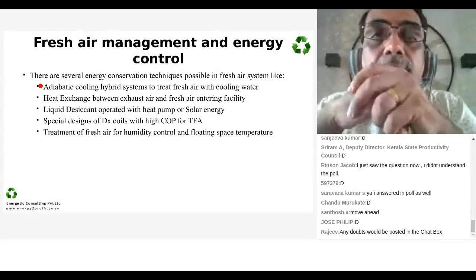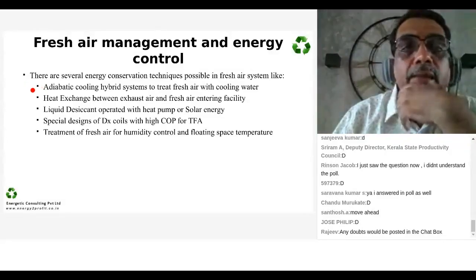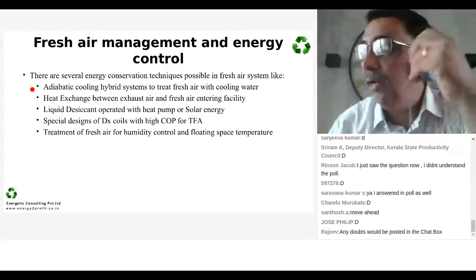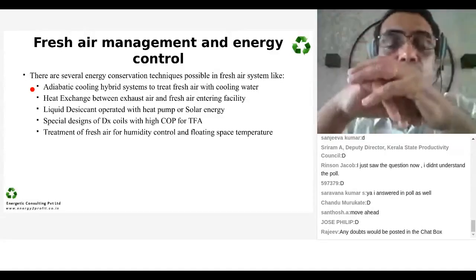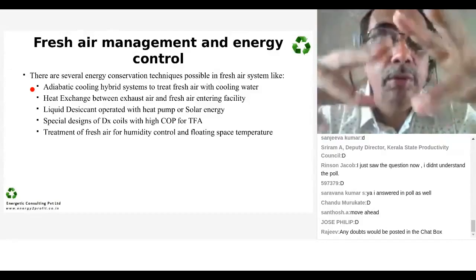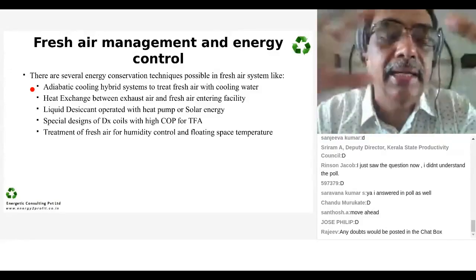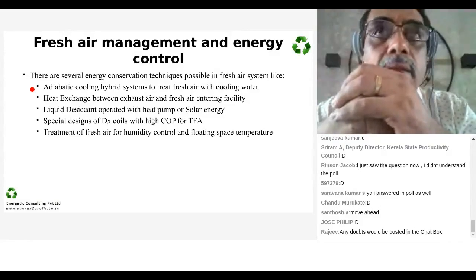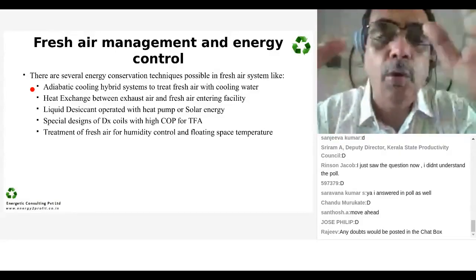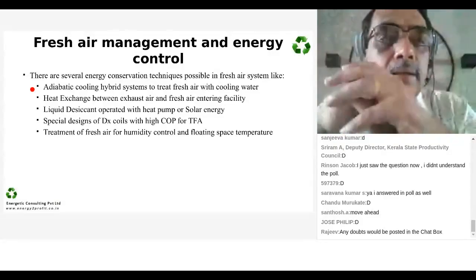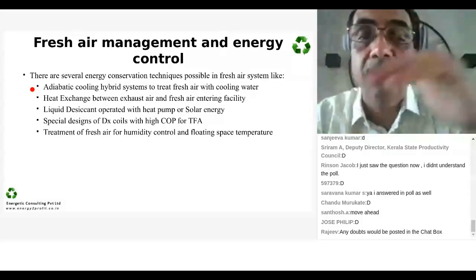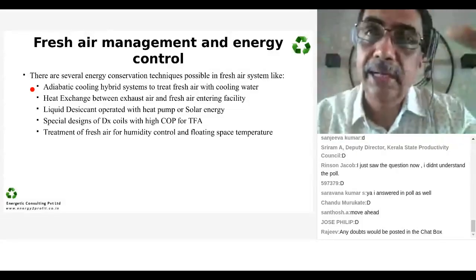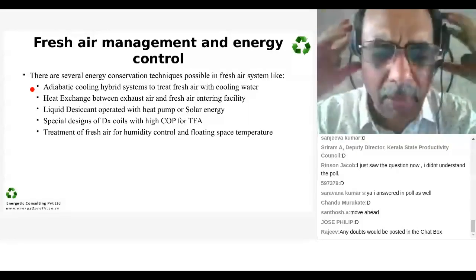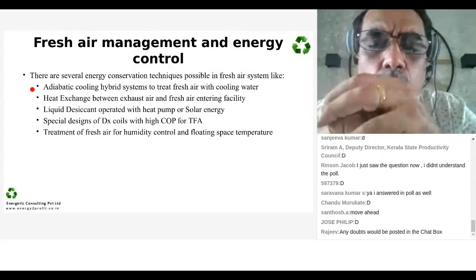Now, what are the methods of energy efficient fresh air management? One, adiabatic cooling hybrid system, which means we are going to have systems where the air coming in is cooled by using a combination of direct and indirect heat exchangers with water. Ambient cooling tower or ambient water, not really chilled water. Another method is heat exchange between the exhaust air and fresh air to recoup the heat. So exhaust is also ducted by design, and fresh air intake is also ducted by design. For example, you have hospitals where you have once-through systems, where you have to throw that air out.